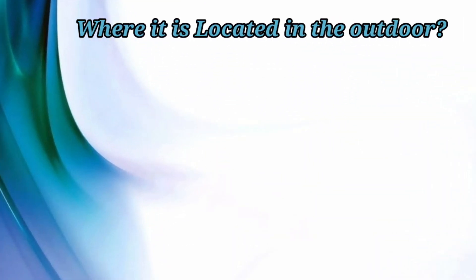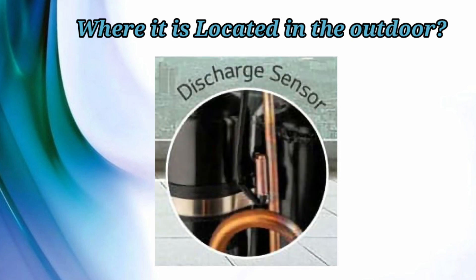The F3 sensor is located on the discharge pipe of the compressor. As you can see in the picture, it is mounted on the compressor discharge. Check that sensor when you encounter error code F3.